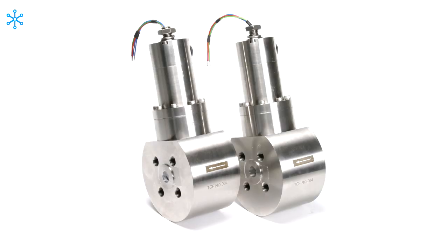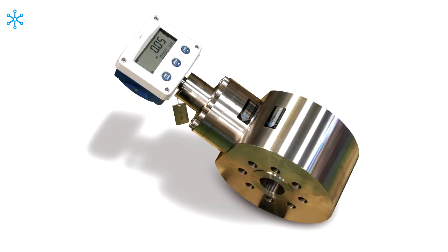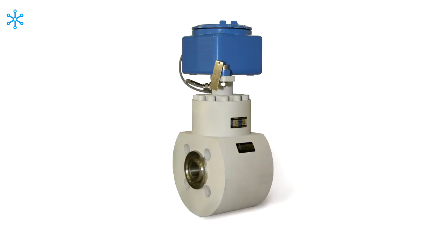The VFF is typically suitable for half-inch connections and larger, perfect for measuring either low flow, high pressure chemicals or hydraulic fluids. The minimum flow rates can drop below 0.01 liters per hour. Depending on viscosity, it caters for a range between 0.8 to 90,000 centistokes.